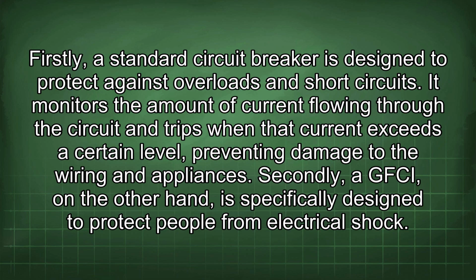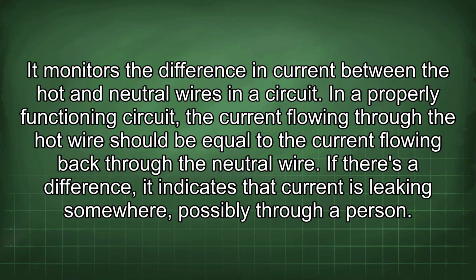Secondly, a GFCI, on the other hand, is specifically designed to protect people from electrical shock. It monitors the difference in current between the hot and neutral wires in a circuit. In a properly functioning circuit, the current flowing through the hot wire should be equal to the current flowing back through the neutral wire. If there is a difference, it indicates that current is leaking somewhere, possibly through a person.